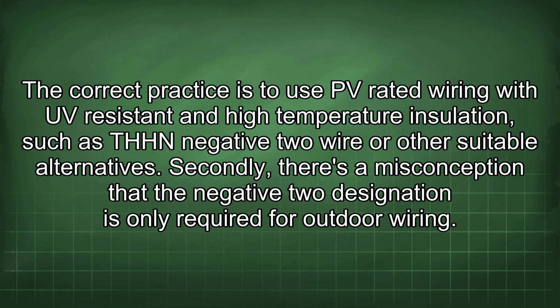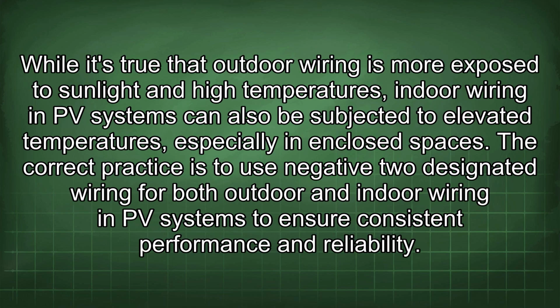suitable alternatives. Secondly, there's a misconception that the -2 designation is only required for outdoor wiring. While it's true that outdoor wiring is more exposed to sunlight and high temperatures, indoor wiring in PV systems can also be subjected to elevated temperatures, especially in enclosed spaces.